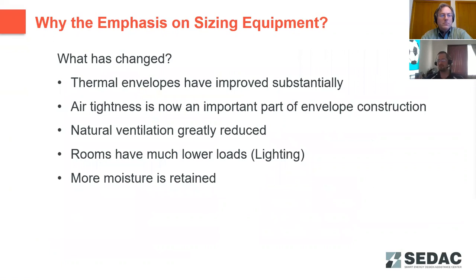So again, covering why the emphasis on sizing of equipment. We've got significantly improved thermal envelopes with higher insulation values. We've got significantly improved air tightness, and so we're not having to oversize equipment to account for leakage through the building. We've reduced natural ventilation and we're going more with controlled ventilation. Rooms have much lower loads as far as lighting and plug-in electronics, as those have become more efficient. And we're retaining more moisture within the house in the wintertime, and we're not drawing as much moisture in from outside in the summertime, so we've got much lower humidity loads. All of these have a dramatic impact on the sizing of the HVAC equipment.